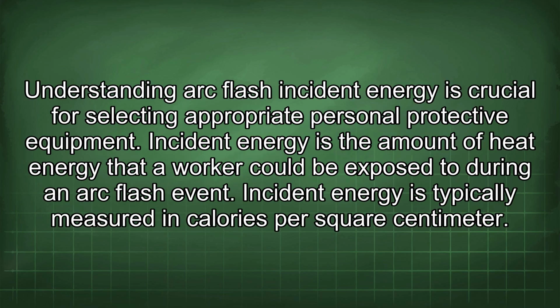Understanding arc flash incident energy is crucial for selecting appropriate personal protective equipment. Incident energy is the amount of heat energy that a worker could be exposed to during an arc flash event. Incident energy is typically measured in calories per square centimeter.